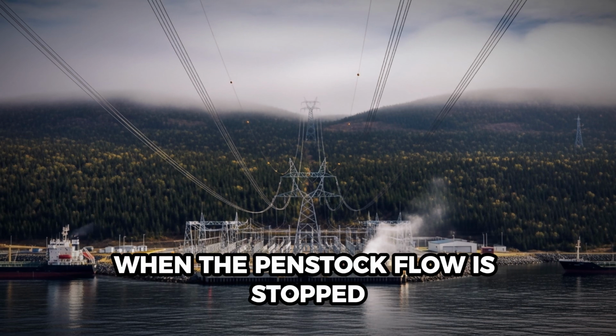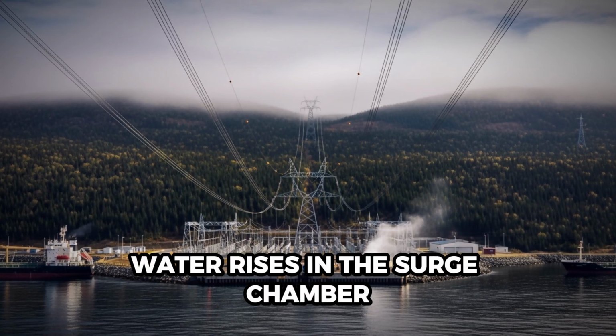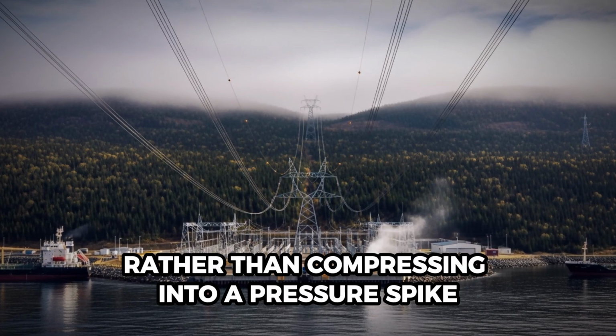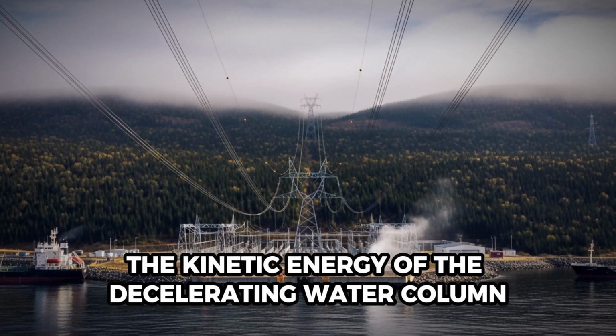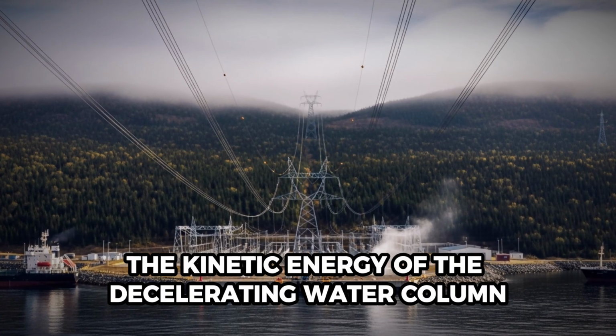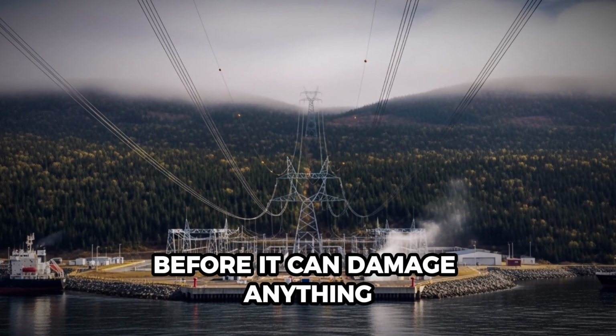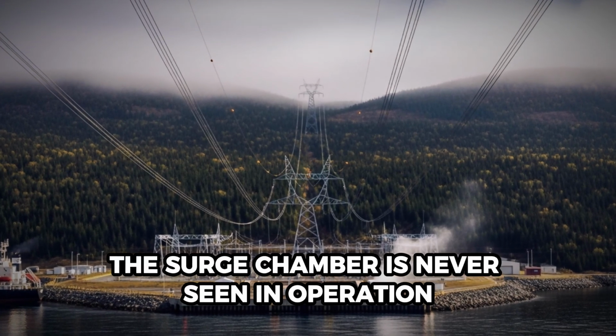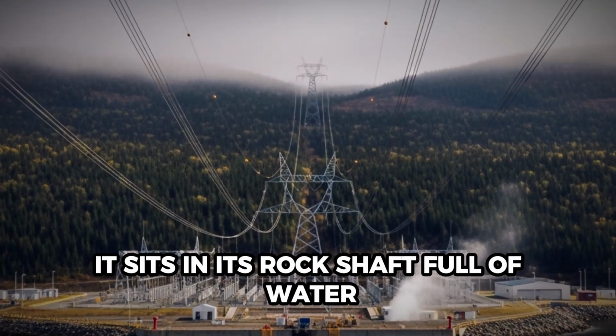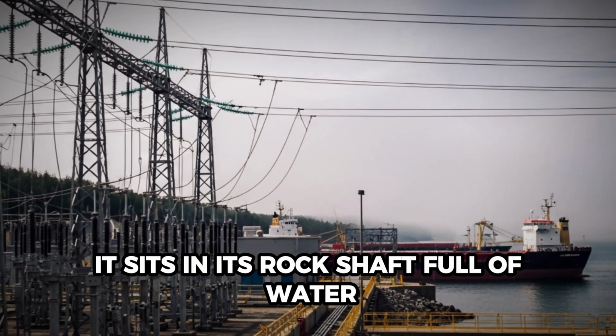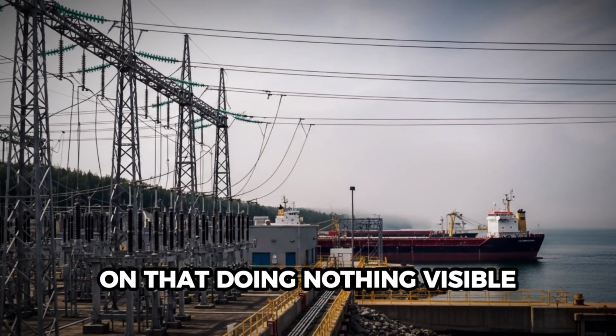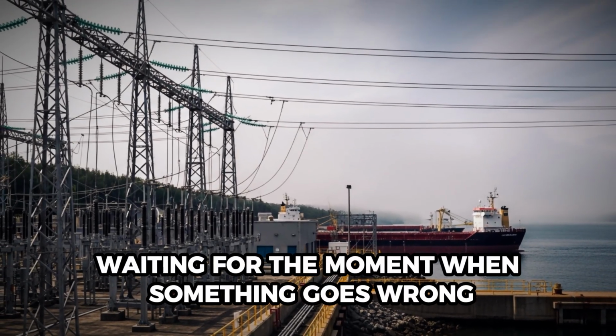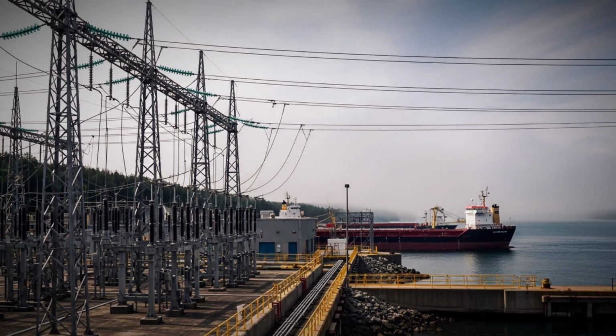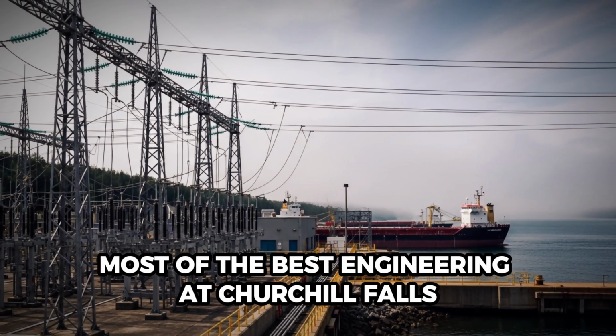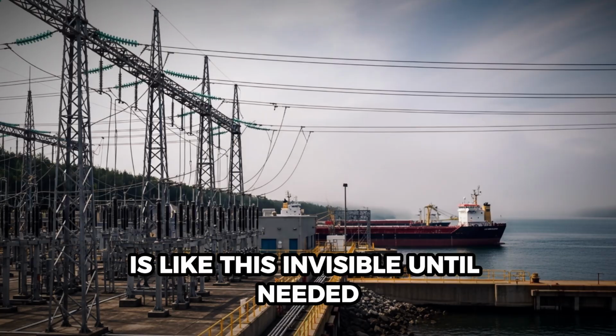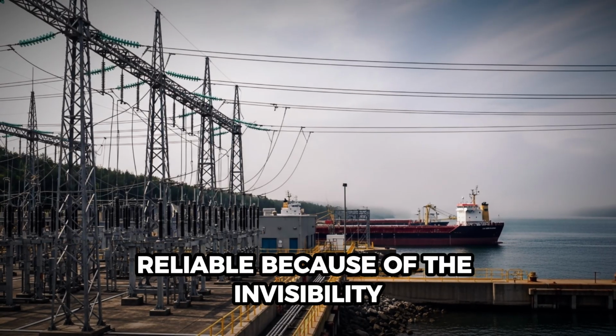When the penstock flow is stopped, water rises in the surge chamber, rather than compressing into a pressure spike. The chamber volume absorbs the kinetic energy of the decelerating water column. The pressure wave is damped before it can damage anything. The surge chamber is never seen in operation. It sits in its rock shaft, full of water, doing nothing visible, waiting for the moment when something goes wrong and its volume becomes essential. Most of the best engineering at Churchill Falls is like this: invisible until needed, reliable because of the invisibility.